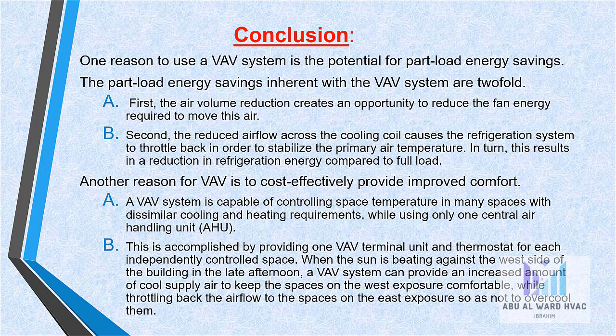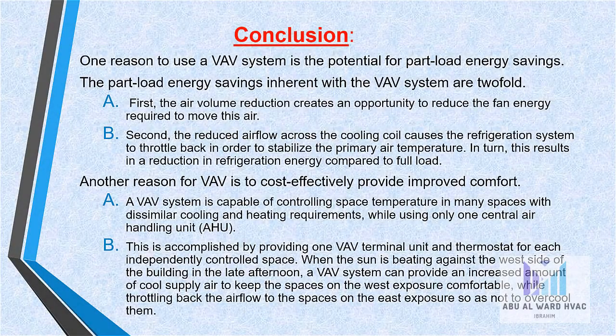This is accomplished by providing one VAV terminal unit and thermostat for each independently controlled space. For example, when the sun is beating against the west side of the building in the late afternoon, a VAV system can provide an increased amount of cool supply air to keep the spaces on the west exposure comfortable, while throttling back the air flow to the spaces on the east exposure so as not to over-cool them.